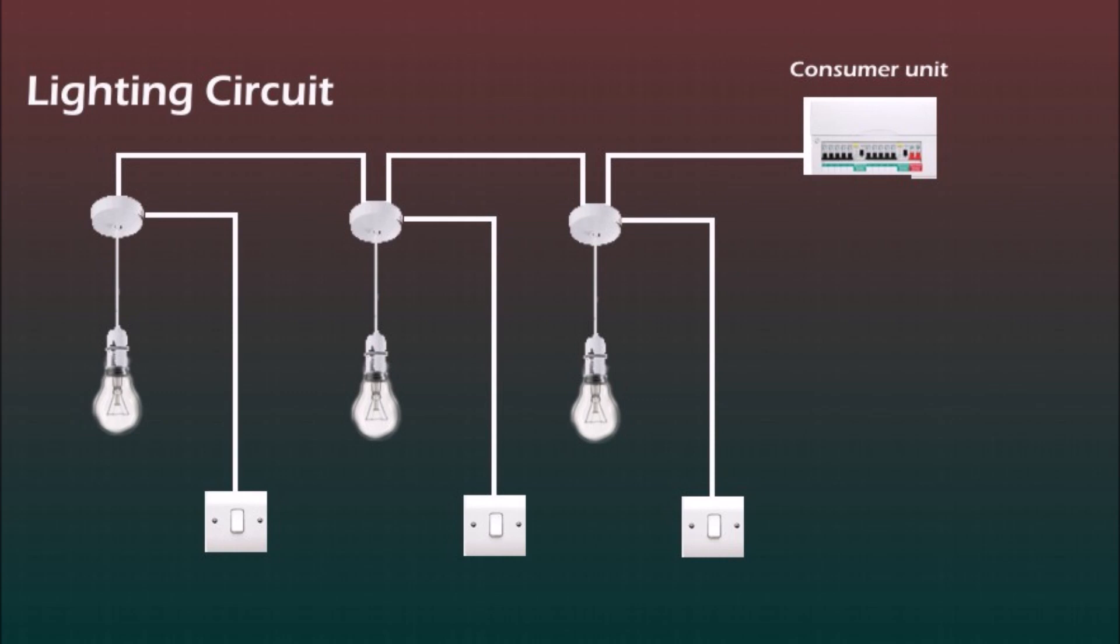But let's say the first lamp is on the staircase and we want to control it from two switches, one from the bottom and one from the top of the stairs. To do this we need to replace the one-way switch with a two-way switch and also add another two-way switch, then link them together with three core and earth cable.